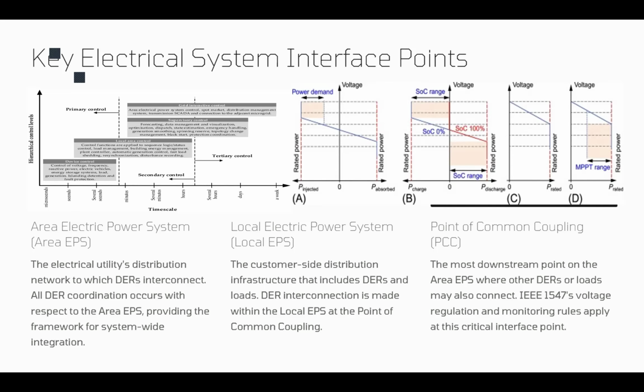Now, the local EPS is the part that has the potential of creating those problems. If we talk about harmonic distortion and we want to control it, it is basically the local EPS that creates those harmonic distortions, and we need to control it. So we make sure the area EPS is not affected by harmonic distortion or any type of challenges. Now, we have two parts, area EPS and local EPS. The point where they meet, we call the point of common coupling.